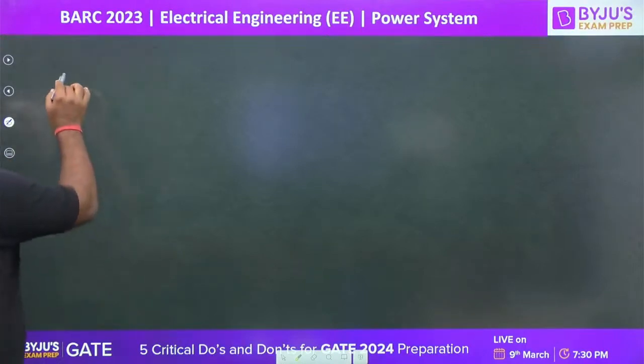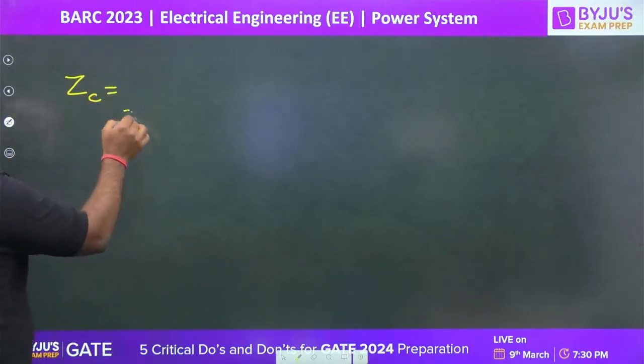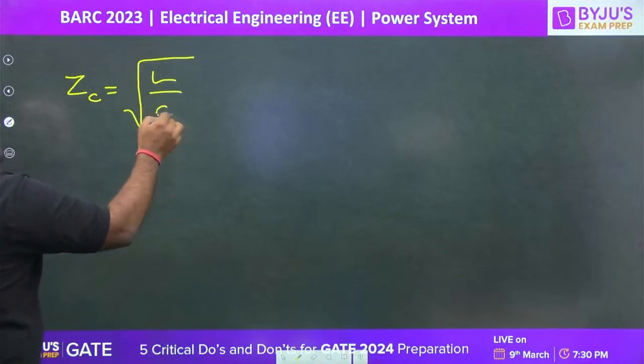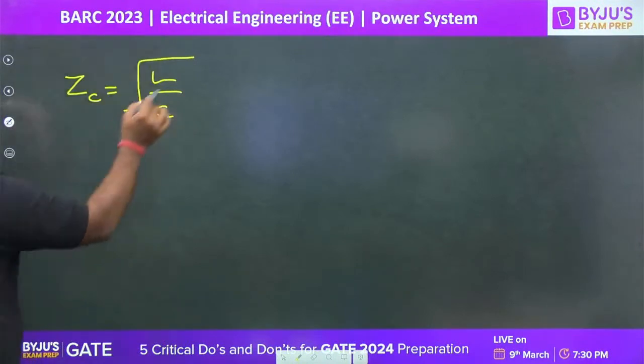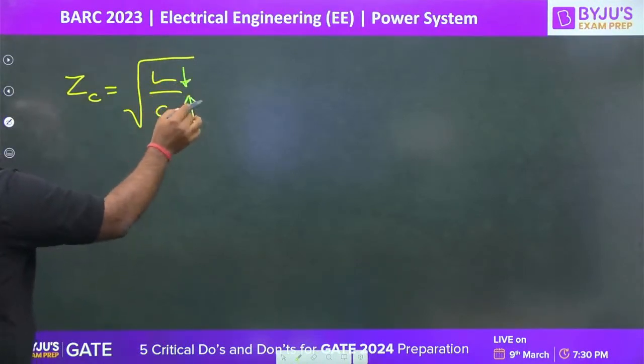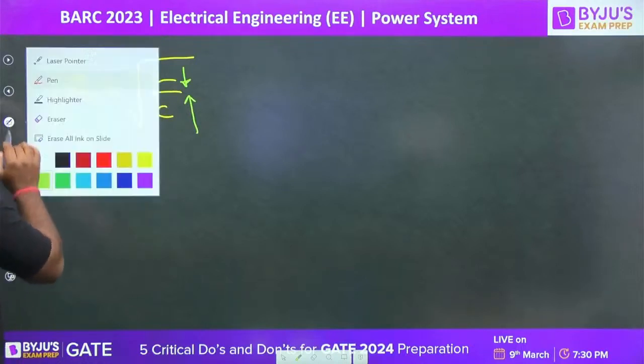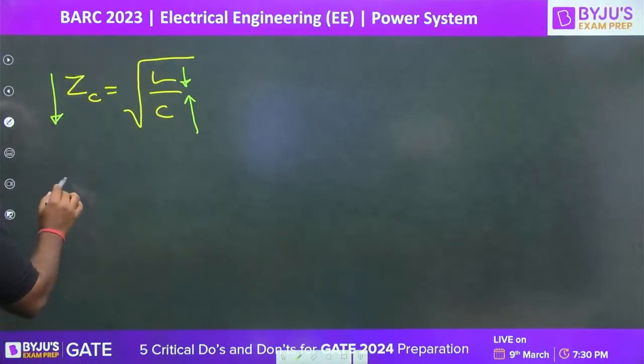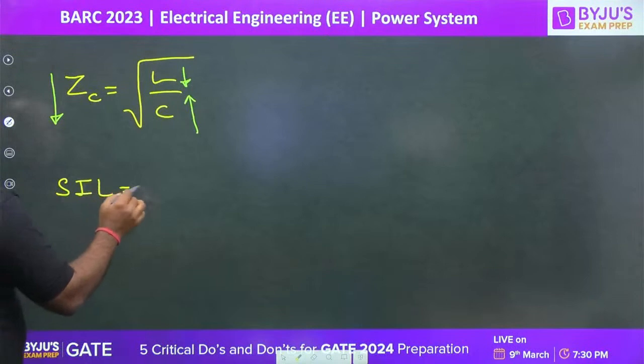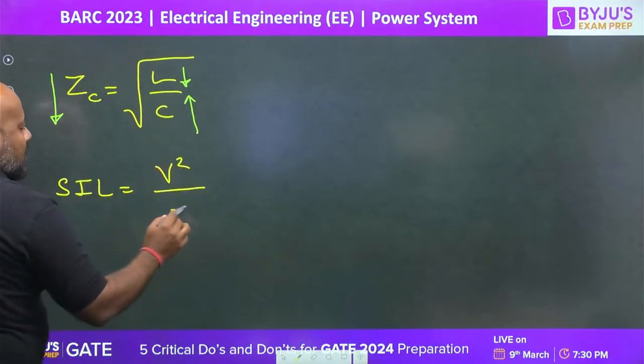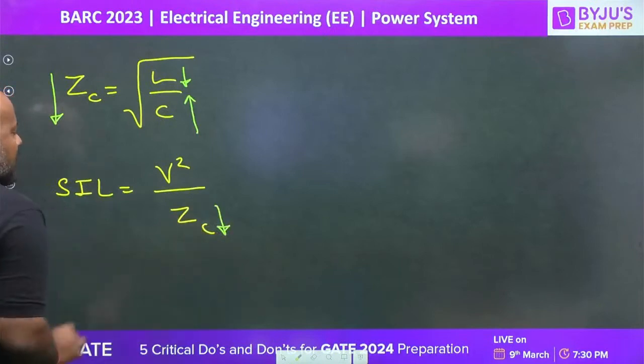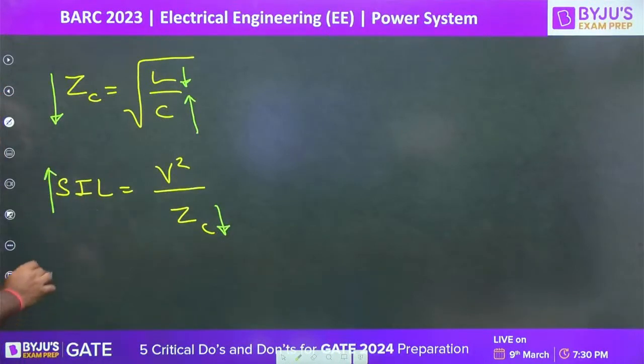Now, if you talk about surge impedance, it is under root L by C. Now, L is reduced, C is increased, so definitely the surge impedance is also going to be reduced. What is going to happen with the surge impedance loading? It is V square upon ZC. ZC is reduced because we are using the bundled conductor, so surge impedance loading is increased.